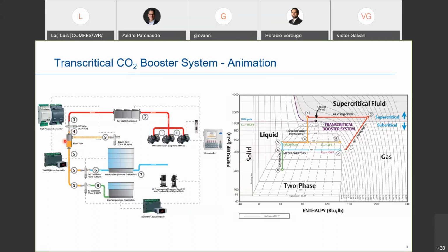And let's say that's 550 pounds. Well, if my head pressure up here, my condensing, keeps going up and down because of ambient, that'll have an impact on the flash tank. So this valve, the bypass valve, opens and closes. It modulates from open to close to bleed off excess pressure in this flash tank to maintain, or try to maintain, a constant pressure in that tank.